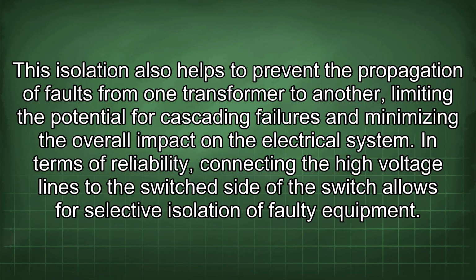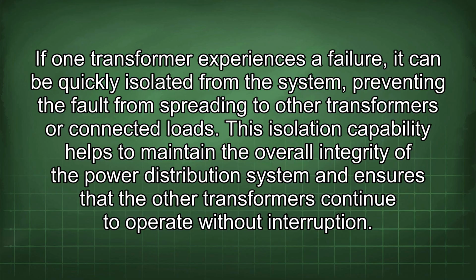In terms of reliability, connecting the high-voltage lines to the switched side of the switch allows for selective isolation of faulty equipment. If one transformer experiences a failure, it can be quickly isolated from the system, preventing the fault from spreading to other transformers or connected loads. This isolation capability helps to maintain the overall integrity of the power distribution system and ensures that the other transformers continue to operate without interruption.